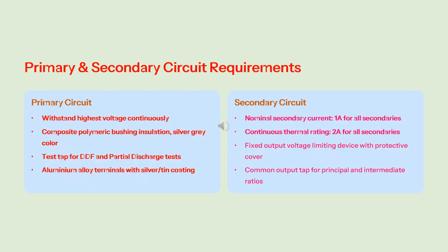Primary and secondary circuit requirements of EHV CT. Primary circuit: first, withstand highest voltage continuously. Second, composite polymeric bushings insulation, silver gray color. Third, test tap for DDF and partial discharge tests. Fourth, aluminum alloy terminals with silver tin coating. In secondary circuit: first, nominal secondary current 1 ampere for all secondaries. Second, continuous thermal rating 2 ampere for all secondaries. Third, fixed output voltage limiting devices with protective cover. Fourth, common output tap for principal and intermediate ratio.